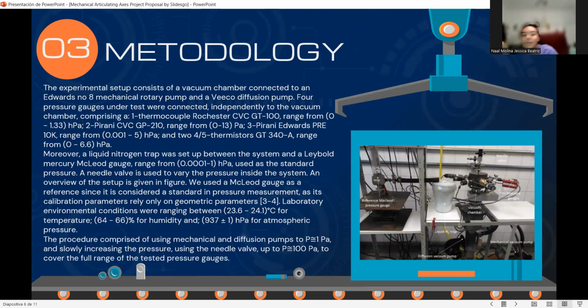Now we are going to talk about the methodology explained in the article. In this case, it consists of a vacuum chamber connected to an Edwards number 8 mechanical rotary pump; we can see an image of what we are talking about. And then a Veeco diffusion pump. The pressure gauges are connected independently to the vacuum. What does this mean? This means that they are separate from the vacuum chamber.